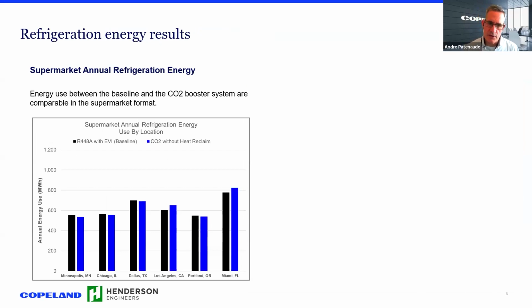Supermarket annual energy refrigeration energy use. Now, if you take a look at the table here, the y-axis is annual energy in megawatt hours, and we have the cities we chose at the bottom. The black bar is 448 with EVI, that's our baseline, and CO2 with adiabatic gas cooling. And you can see that in most of the cases, CO2 is marginally better, except for Los Angeles, it's slightly higher, and Miami is slightly higher. There's more hours of operation, bin hours, in the warm ambient areas than the other cities. So that's supermarket, 57,000 square feet with 35% of the low temp load to total.